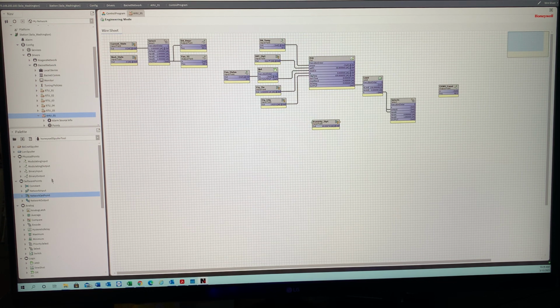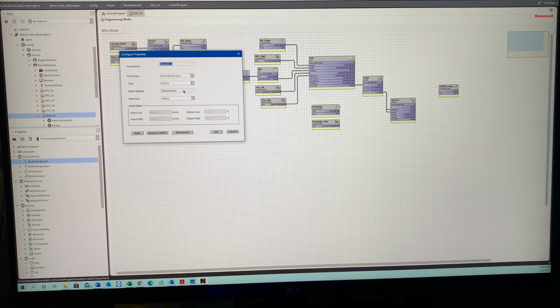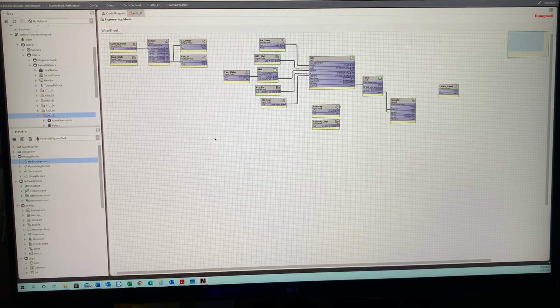So then we need a modulating input. I'm going to call this humidity. We could do zone humidity, but let's try and keep this real basic for right now. So we're going to go configure properties. Like I said, I'm just trying to show you guys some things. We can expand on it more and more as we go. Ours is going to be custom voltage. It's going to be percentage. We're going to say 0 to 10 volts, 0 to 100% on the humidity. Click OK. There's one thing I wanted to check on this.